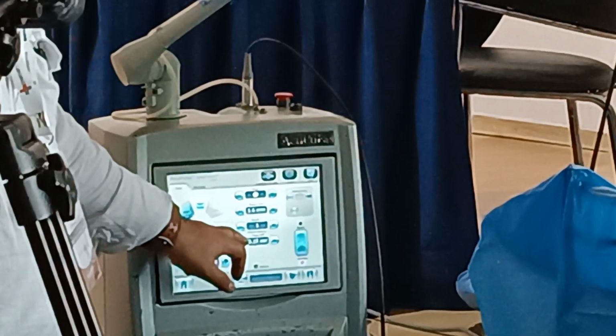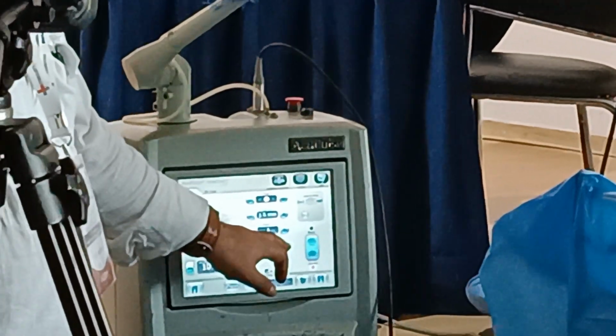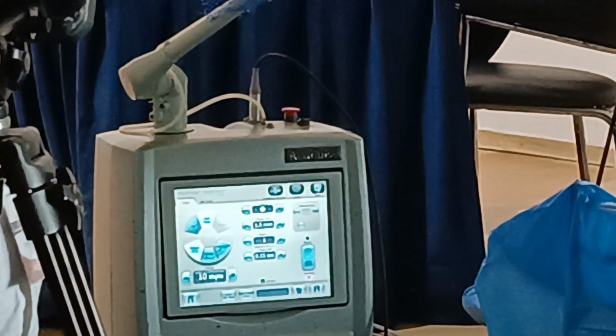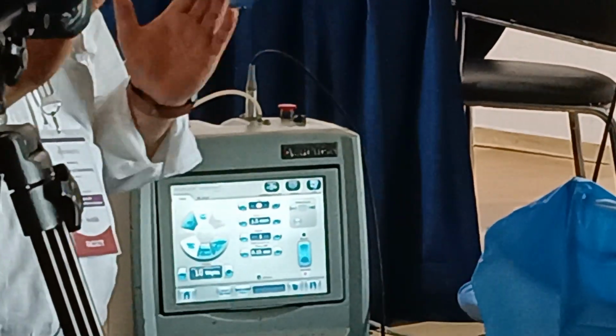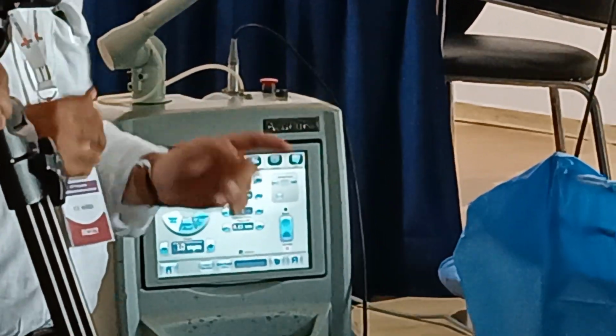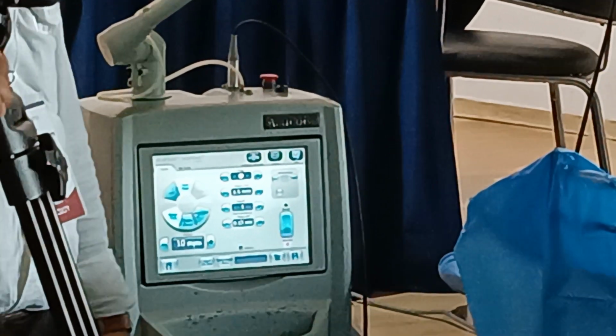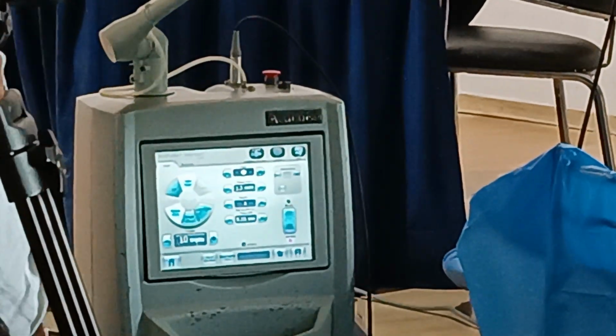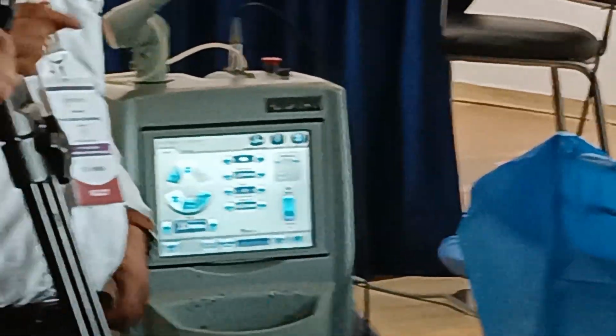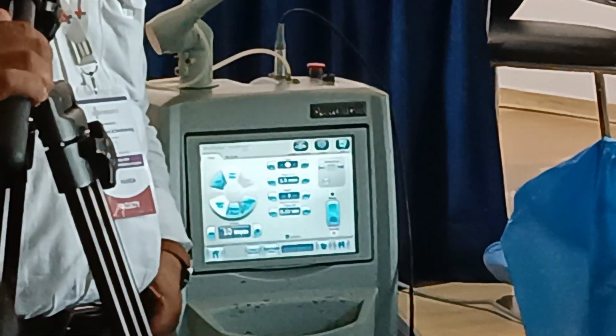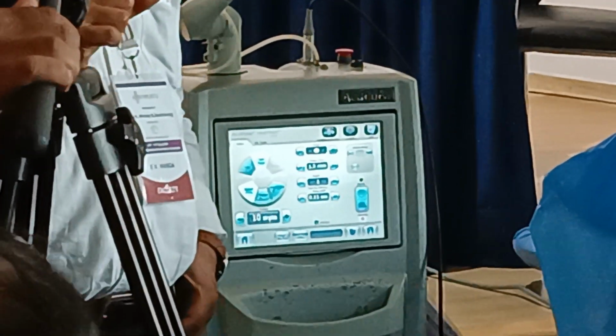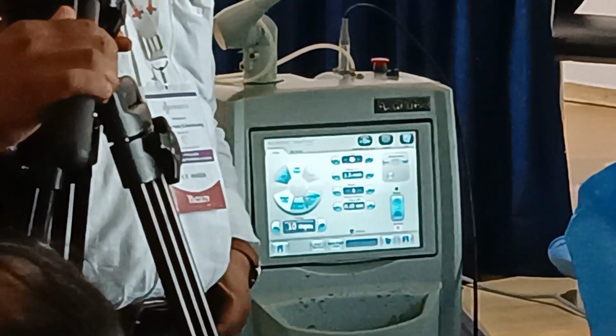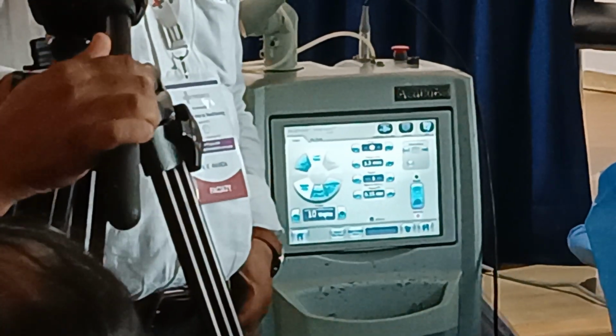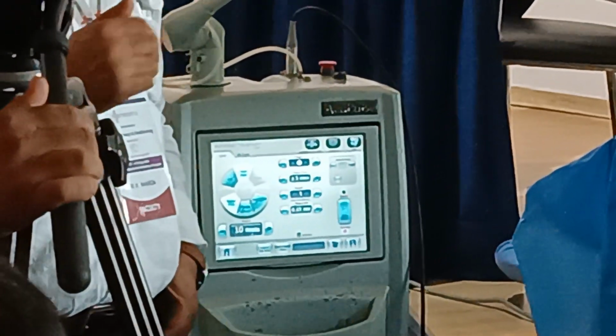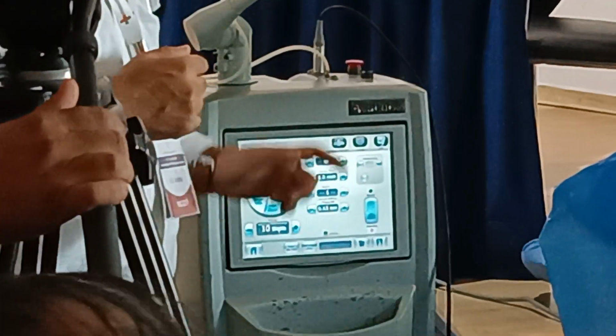The timer is, now you will see once we fire, if I keep it at 45, the power will not be there. It is the time between the shots. Here if you keep it at 50, it will cut very fast. You will see actually when we use the aiming beam. Now see this CO2, the wavelength is 10,600 nanometers. This is beyond the visible spectrum. Visible spectrum is somewhere from 400 to 600 nanometers. This means the naked eye cannot see the CO2 laser beam. So we use an aiming beam.